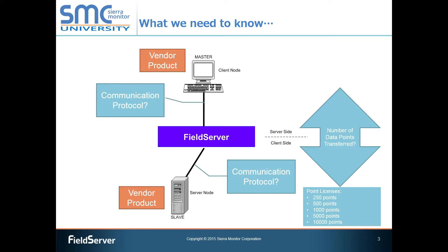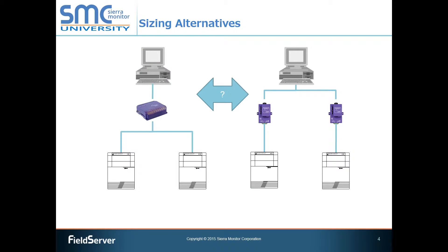When calculating the number of data points to be transferred, please keep in mind that we only need to know if the number of data points exceeds certain thresholds that guide us to choose different hardware or point licenses. Those thresholds per field server occur at 250 points, 500 points, 1,000 points, 5,000 points, and 10,000 points. You will also need to consider whether the data points are being split between multiple field servers for practical or performance reasons.